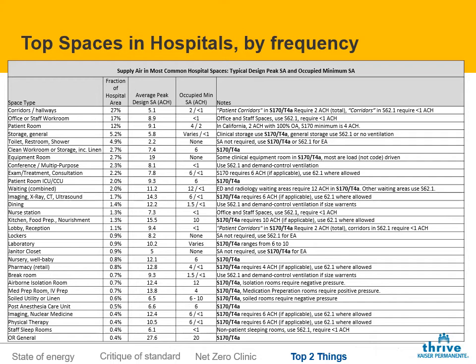Exam rooms, I think I've already sort of talked about based on the outpatient stuff. The 6 air changes that's in the code is kind of silly, but our designs are coming in at 8 air changes. And so you can turn those down to 6 air changes during operating hours, and you can turn it down when they're unoccupied. Worst case is California, where you can turn it down to 25% when it's unoccupied. So your overnight minimum there will be 2 air changes, right?